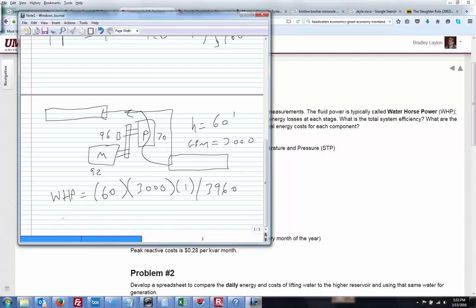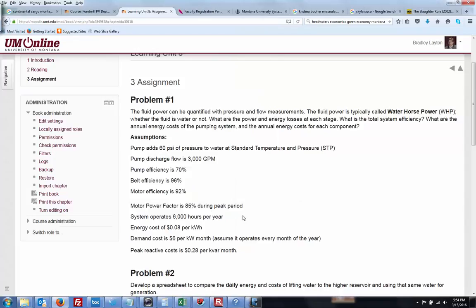So we'll get that. And then the power is going to equal the WHP times eta motor, divided by, right? Yeah. Because the number's got to get bigger, because you're going to put more energy in than you get out. So divided by eta motor, divided by eta belt, divided by eta P. So that's just pretty much straight up algebra. So the water horsepower, multiply those three numbers, divide by that fourth one, plug it in here, divide by your three efficiencies, bam, bam, bam, is going to give you your power. Okay.